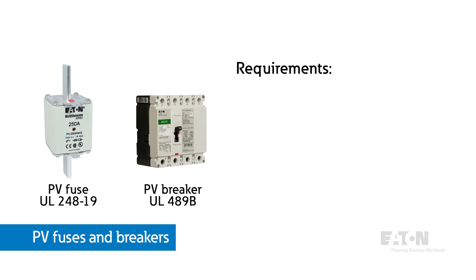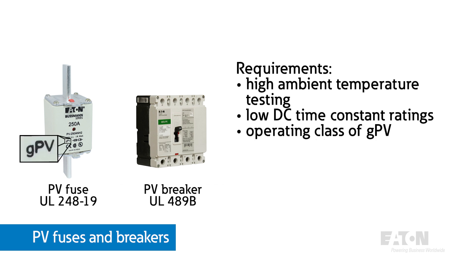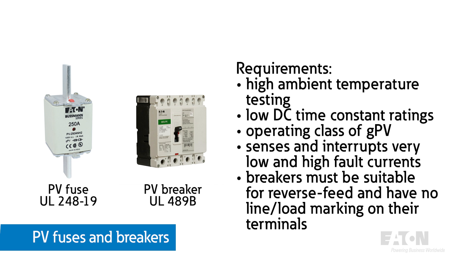These requirements include higher ambient temperature testing, low DC time constant ratings, and an operating class of GPV, which means it is a full range overcurrent protective device capable of sensing and interrupting very low and high fault currents. Additionally, breakers must be suitable for reverse feed and have no line or load markings on their terminals. It's important to note that many of these DC devices are suitable only for their specific application and are not permitted to be used in any other types of circuits. Since so many energy transition applications link multiple DC systems together, it becomes critical to understand where one system ends and the other begins. The type of overcurrent protective device you use will be dependent upon which system it's protecting.